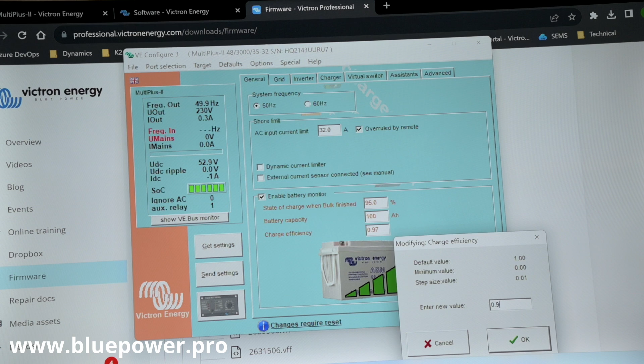The next option we've got here is our grid. This unit has already been configured previously on the South African grid code, but out of the box, the unit is going to come on none. So feeding energy to the grid is not allowed at all. You can't run ESS on none as well, so it is required to select the grid code. If you are installing in Cape Town a MultiPlus II inverter, then you must select the South African grid code. So we've selected the South African grid code.